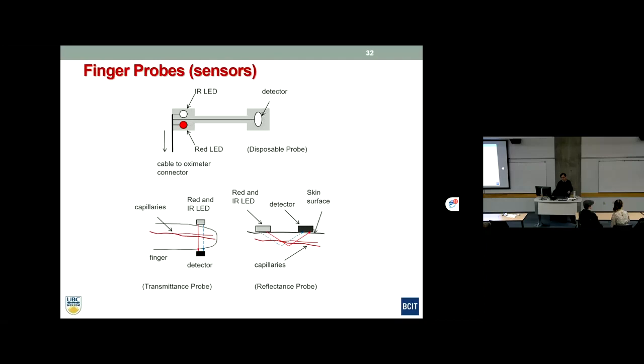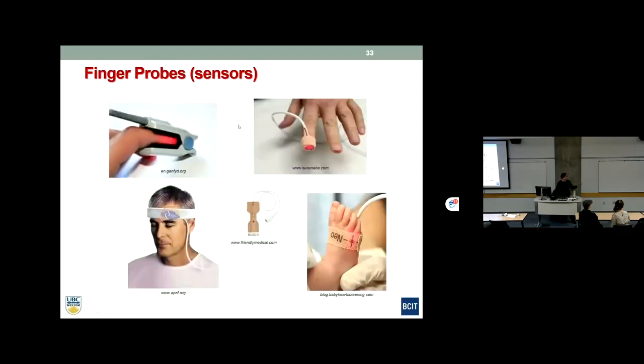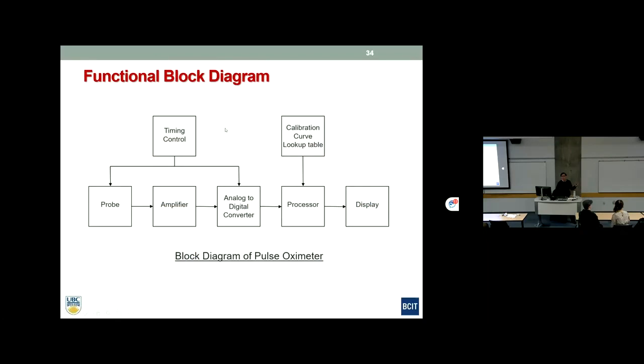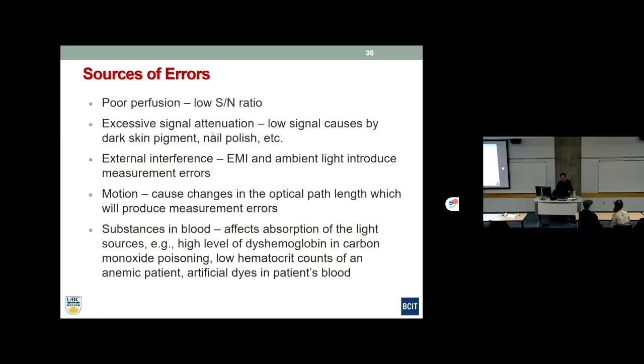There are different probe types: a transmissive probe with LED on one side and detector on the other, and a reflective probe where both transmitter and receiver are on the same side of the skin, detecting reflected or scattered light. These probes can be deployed in various configurations. There is also a functional building block diagram to allow engineers to design and manufacture this device.